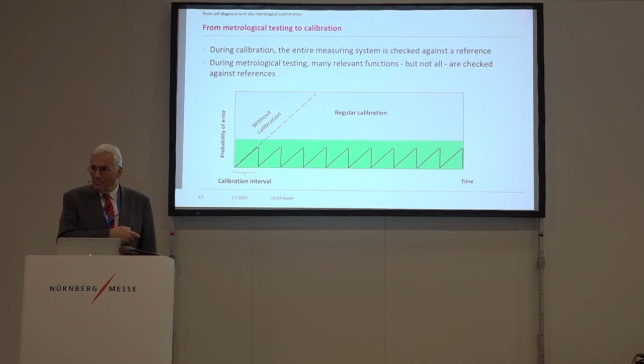Okay. Now, let's look at the same with internal metrological testing. You also have this curve when you do nothing, but then you do regular internal metrological testing. This looks pretty much the same, but it's getting worse because you don't affect all parameters. Maybe you only cover 90% or 80%. There's still a probability going up that it's getting worse and worse. In order to keep this under control, you do a real calibration, but with a new calibration interval, which is much longer. And just by this internal testing, even when it doesn't affect all components which are relevant for the metrological quality, you may have a drastic increase in the calibration interval.